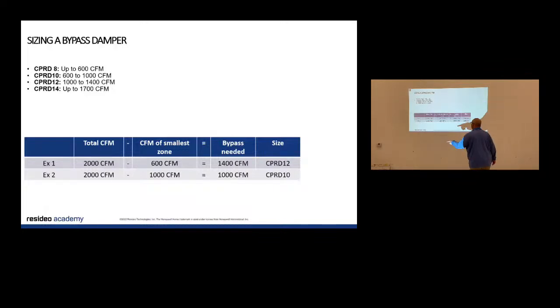This is in the selection guide. We make different size bypass dampers, and this is pretty easy to do. So I've got a 2000 CFM system. My smallest zone is 600. So when I do 600 in the smallest zone, I've got to dump 1400 CFM somewhere. So I go up to the selection guide. I've got 1400 CFM, I've got a 12-inch. That right there is in your book, so you don't have to dig for it anywhere. But that's how you size these. Most guys that do zoning will know, but in case you need to know, it's in the book. It's in the middle page on the very top, and it has that math for you.